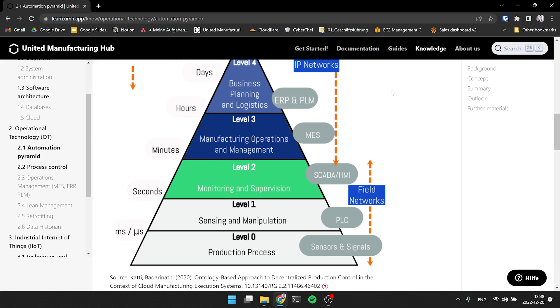And my personal opinion is that we should leave the automation pyramid as it is, but on the right side, basically here, put in a unified namespace. So the data does not only flow across the levels, but also to the right side into a central message broker, for example. So that there you have access to all the data, because when you work with the data, you don't need to ensure that the production keeps running, you're not controlling things. So there you can just send all the data into it, and then you can do data analytics, OEE, and other use cases that you have in industry 4.0 and industrial IoT.